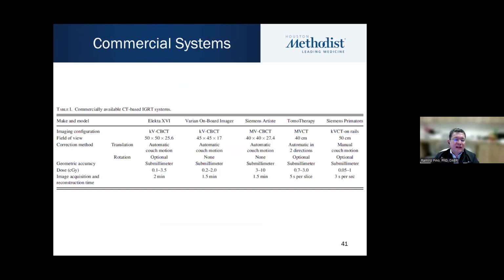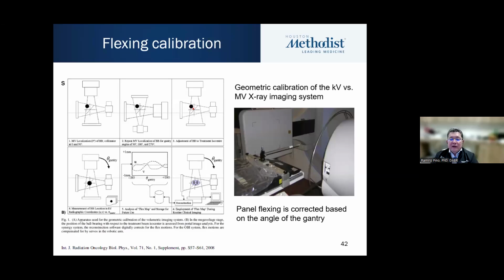So this is a list of the commonly available CT-based IGRT systems. The Elekta XVI, the Varian Onboard Imager, Siemens Artiste, Tomotherapy, and Siemens Primatom, which I haven't seen one in a long time. Basically, because you have a mounted imager, the detectors, whether it's the MV detector or the kV detector, and even the kV source, they will flex, they will change position depending on the gantry orientation, and that needs to be corrected. It's called panel or detector or source flexing.